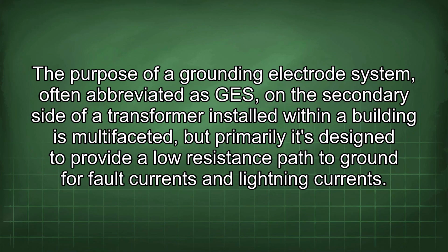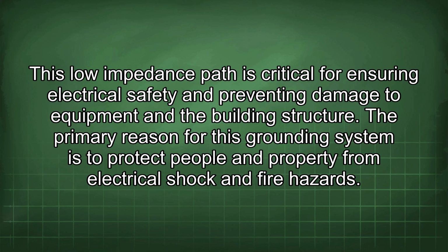The purpose of a grounding electrode system, often abbreviated as GES, on the secondary side of a transformer installed within a building is multifaceted, but primarily it's designed to provide a low resistance path to ground for fault currents and lightning currents. This low impedance path is critical for ensuring electrical safety and preventing damage to equipment and the building structure. The primary reason for this grounding system is to protect people and property from electrical shock and fire hazards.